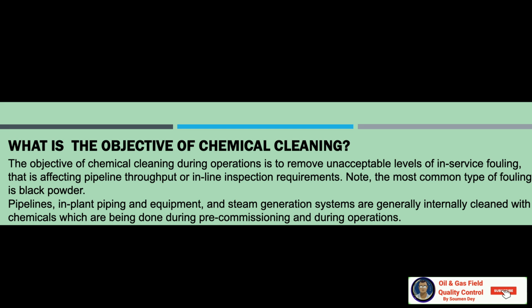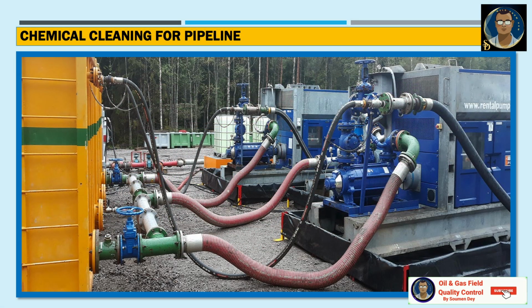First, let us know what the objective of chemical cleaning is. The objective of chemical cleaning during operation is to remove unacceptable levels of in-service fouling that is affecting pipeline throughput or inline inspection requirements. Note, the most common type of fouling is black powder. Pipelines, in-plant piping equipment and steam generation systems are generally internally cleaned with chemicals, which is done during pre-commissioning or during operations. Chemical cleaning is mandatory for pipelines based on standard best practice of the oil and gas industry.